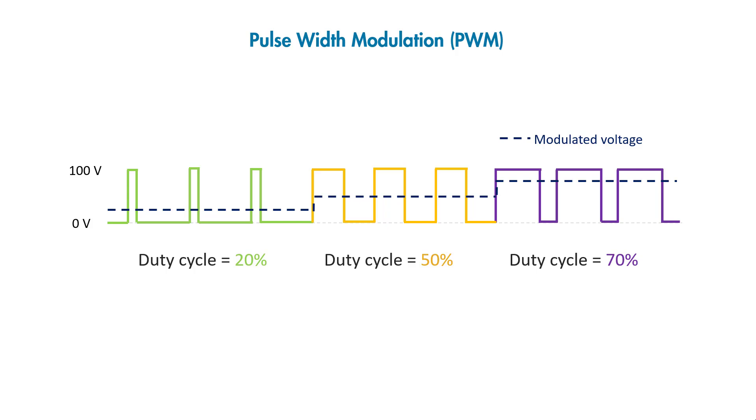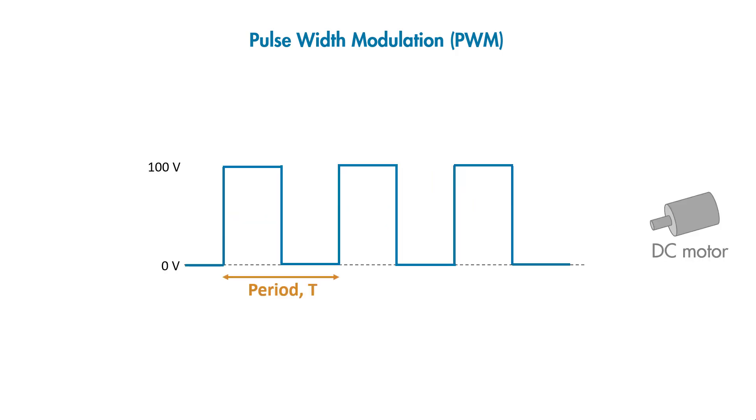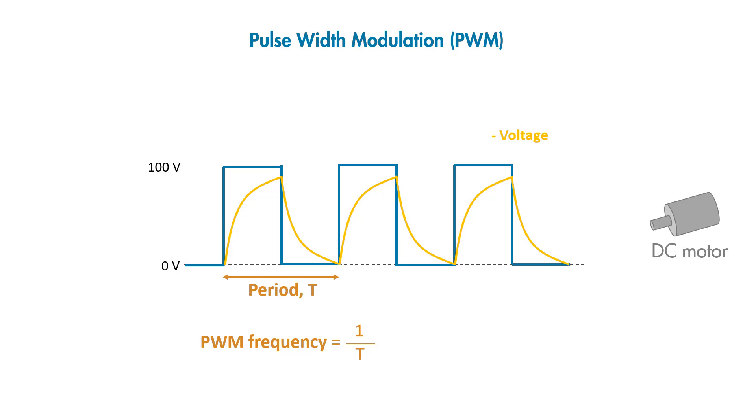Note that the longer the duty cycle, the higher the voltage we get. Now we know PWM control has an averaging effect on the output voltage that is seen by the motor. To get this averaging effect right, we should be careful when selecting the PWM frequency, which is computed by 1 over period. If the switching frequency is too low, instead of seeing an average voltage, the motor will see a voltage that tries to follow the square wave shape. This will lead to poor tracking of the reference speed, and the motor will keep speeding up and slowing down.